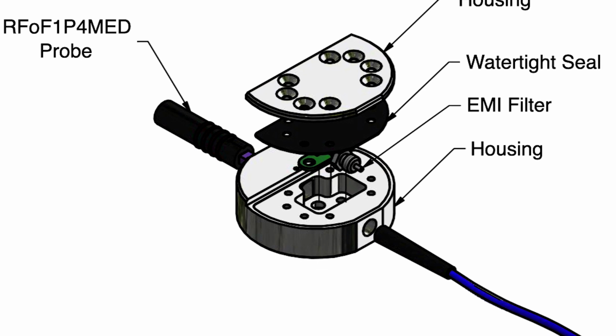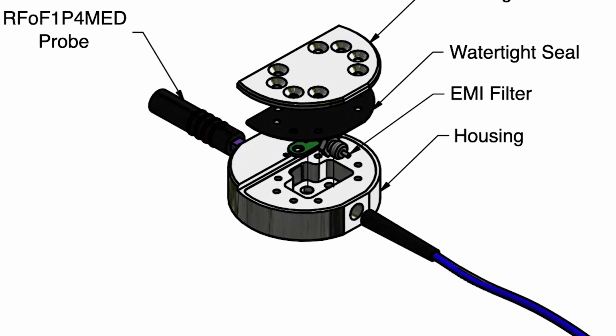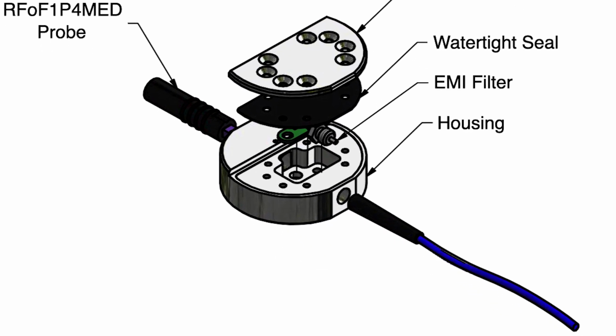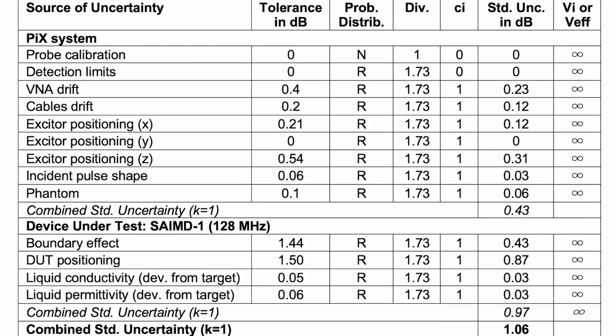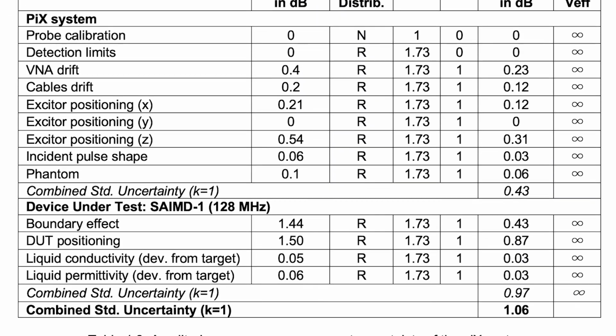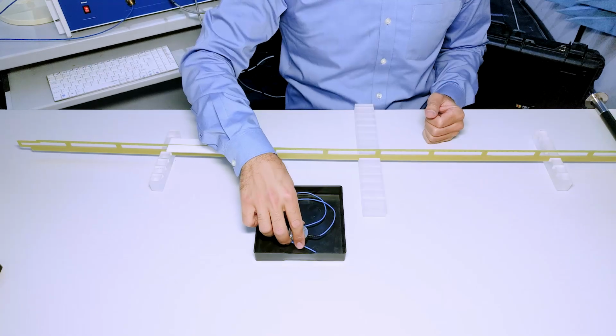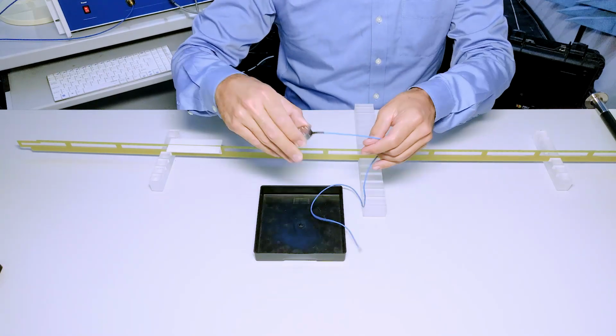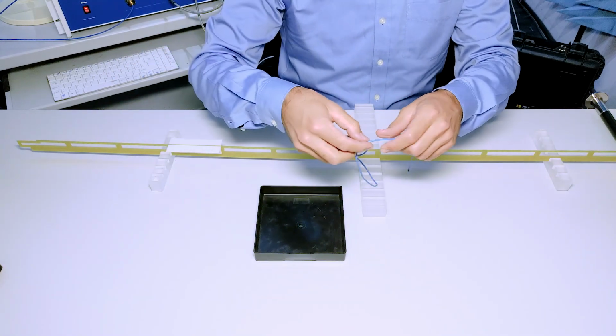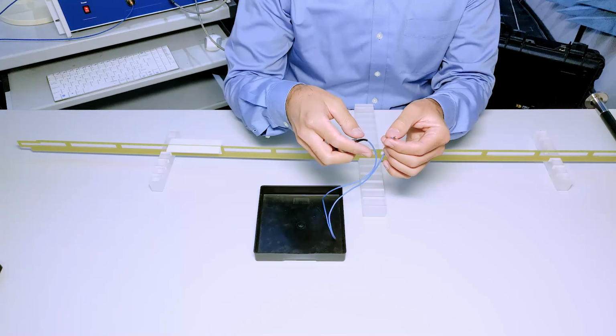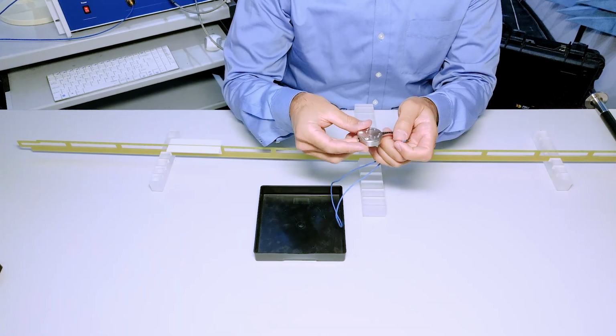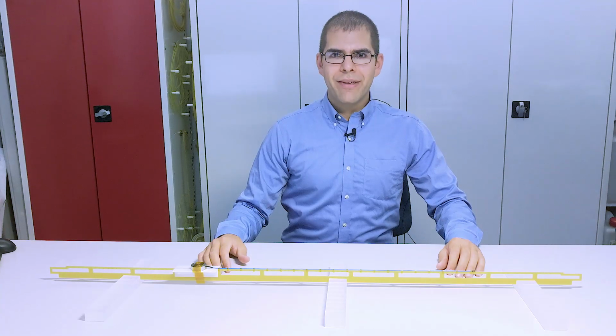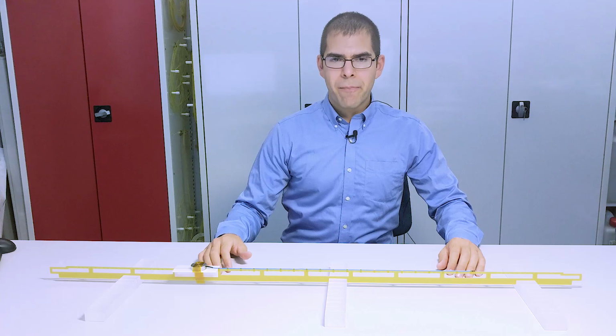This allows us to derive accurate target values to be used for the validation of the measurement instrument and the procedure. The uncertainty of these can be considered to be largely independent of the complexity of the implant. We will now measure the same parameters with this device and compare it to the target values. If we find an agreement within the combined uncertainty bounds, we will consider the measurement setup and applied procedure to be validated. First, we'll make a piecewise excitation measurement of the implant with the PiX system from Zurich MedTech.